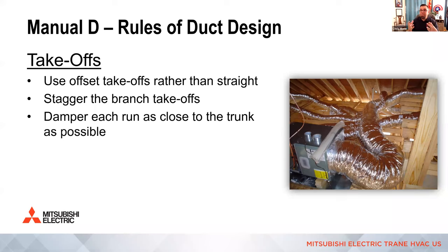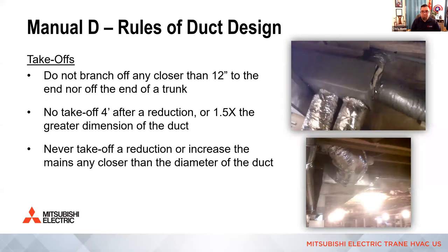If you're going to add dampers, don't put them at the register and don't use the register adjustment as a way of balancing because it's going to be noisy when the system cranks up, because now the free area is lower and your velocity goes up to move the same volume of air through it, okay? Or it's going to be too restrictive on a PSC style motor and decrease the volume of air going to that space. So always put the dampers as close to the trunk as possible to avoid noise and get the right volume of air out.